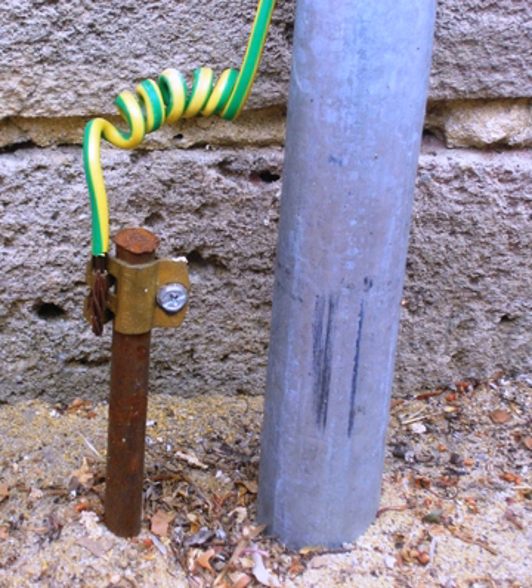On wet construction sites or in shipyards, isolation transformers may be provided so that a fault in a power tool or its cable does not expose users to shock hazard. Circuits used to feed sensitive audio, video production equipment or measurement instruments may be fed from an isolated ungrounded technical power system to limit the injection of noise from the power system.